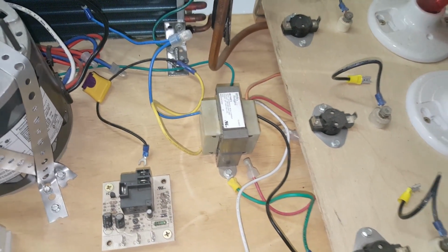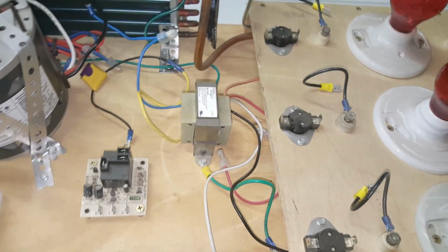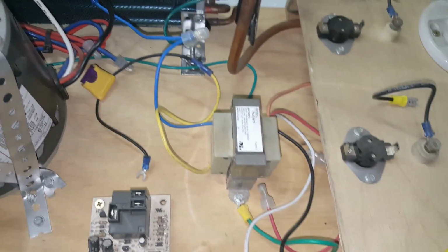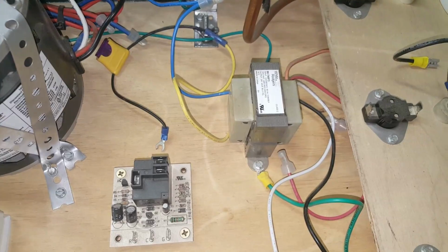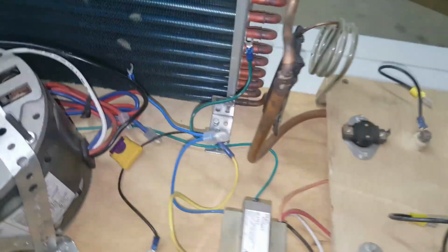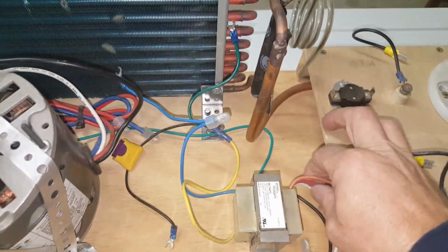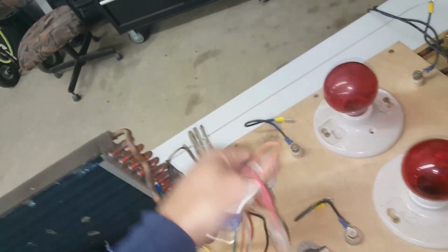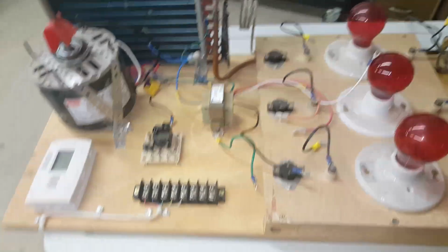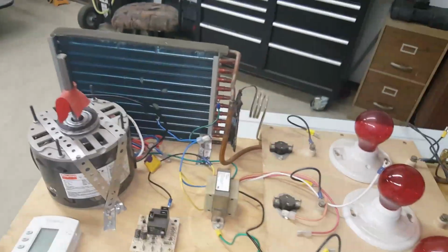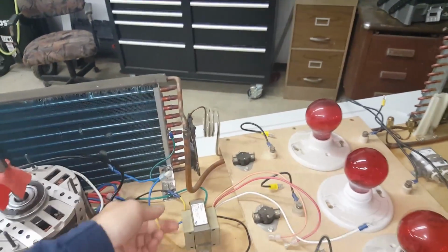But it's also a safety issue with the homeowner. The homeowner will be actually operating the thermostat and could possibly open it up and get electrocuted, so we want to step down to 24 volts for those reasons. You have a primary side of your transformer and a secondary side. This is a multi-tap transformer here, and that's why you have all the different wires. We can actually use this transformer for a 120 volt application, a 208 application, or a 240 volt application on the primary side. And whichever voltage we use, it will step down to the 24 volt side.